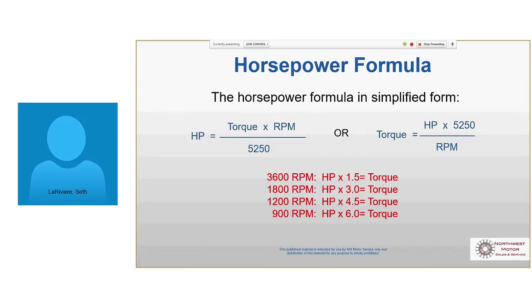This is that little formula. I gave you this one before. There's also a little cheat sheet. If you're dealing a lot with 3,600 RPM motors and you're curious what the torque is on those, it's 1.5 times the horsepower, and then all the way across down for the other speeds.